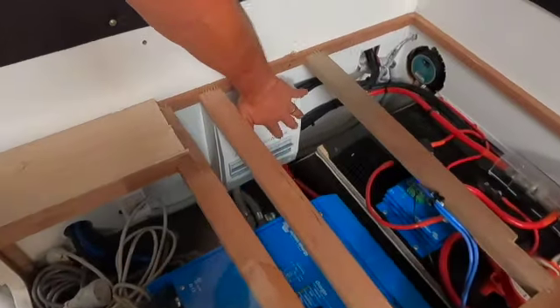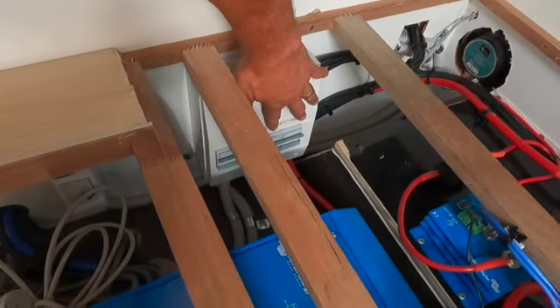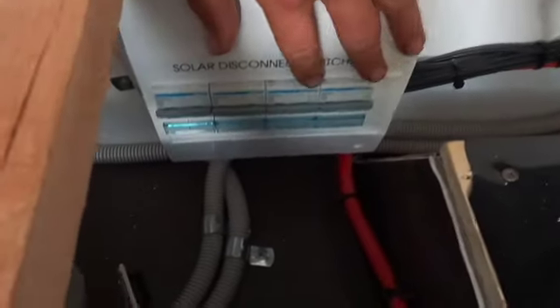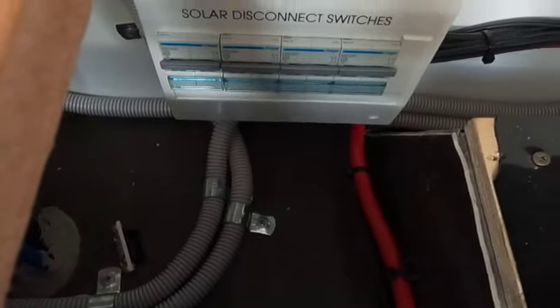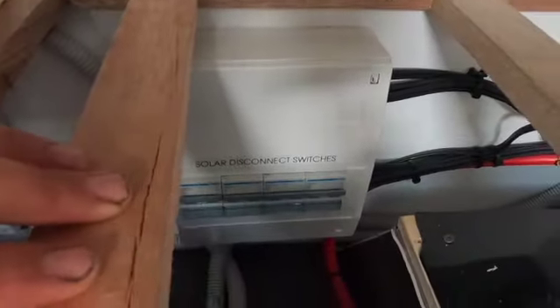These are double pole, double throw AC circuit breakers. I'm just using those as isolators for the solar input, so the PV input goes through those, just so I can isolate the system if I need to work on the MPPTs, or isolate one of the circuits. I just turn these circuit breakers off. They're just Hager circuit breakers, double pole double throw, so they're isolating both the negative and the positive from each of the strings up on the roof.